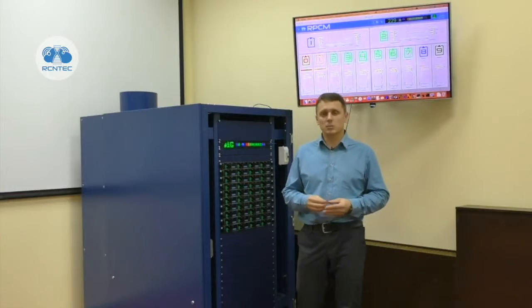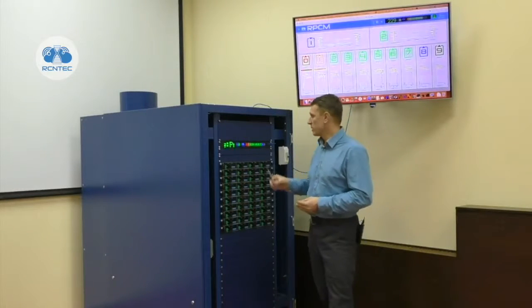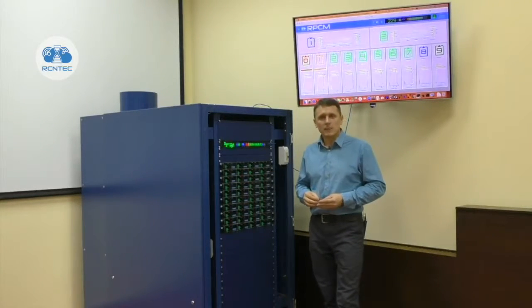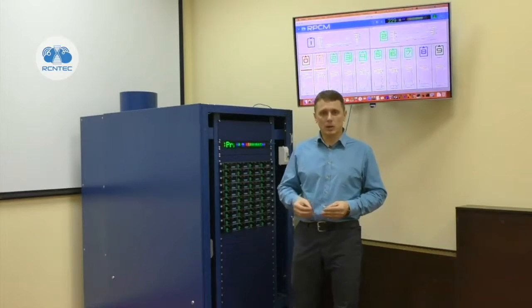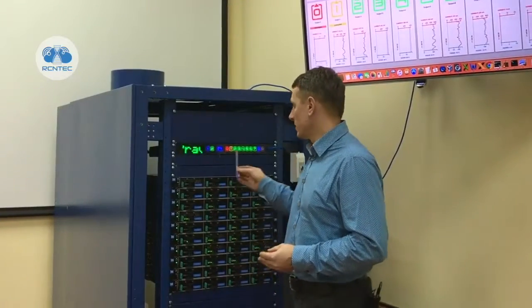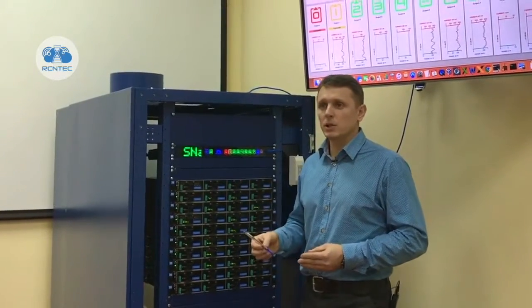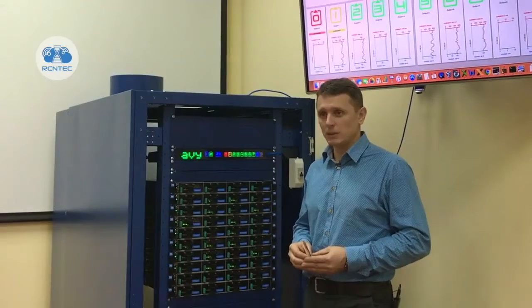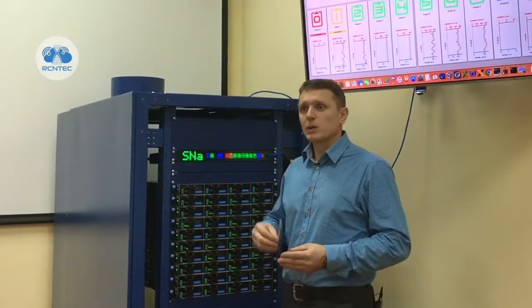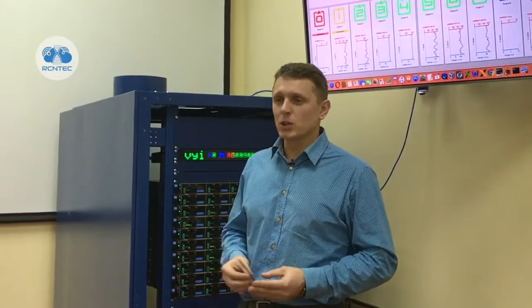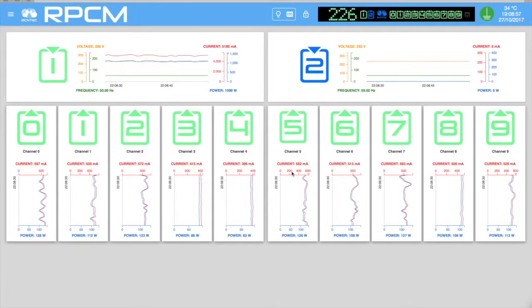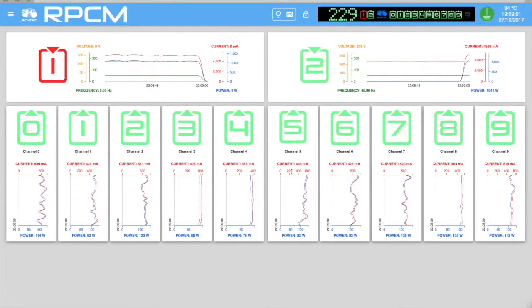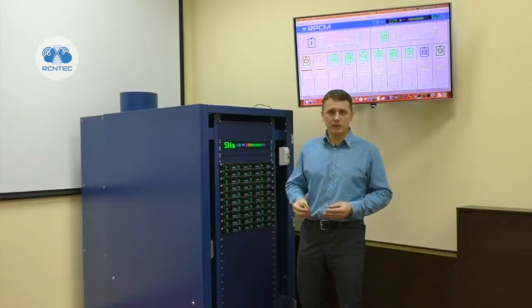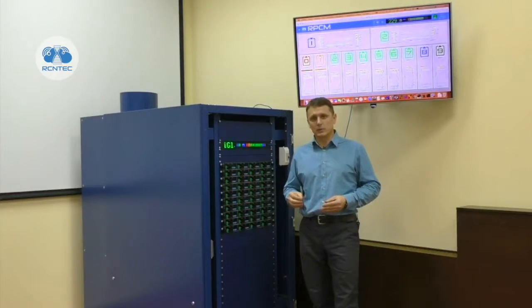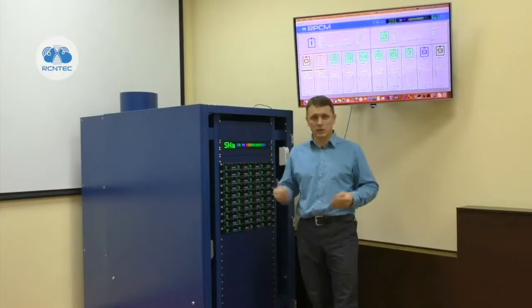First of all, it's fire protection. How does it work? The administrator can set up 2 current consumption limits for each outlet. If the first limit is reached, RPCM notifies the administrator and the external monitoring system about it. If the current continues to rise and reaches the second specified limit, RPCM forcibly cuts off the power supply to that outlet. This way, we engage proactively to prevent fire before it may occur, so overall fire safety is improved.